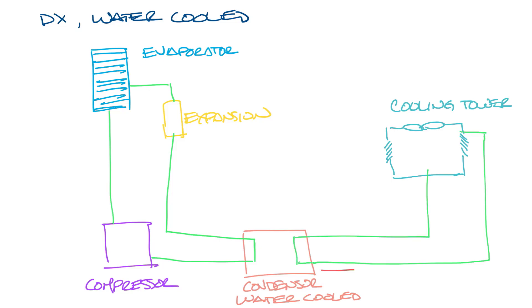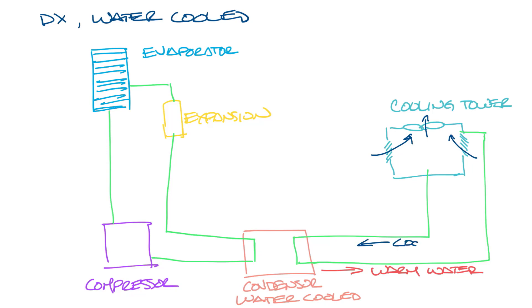Now let's draw in the water loop. The water that is heated up in the condenser travels into the cooling tower. This water is sprayed into the top of the cooling tower. The cooling tower has a fan to draw air across water from the condenser. This causes some of the water to evaporate and cool, and the cooled water falls to the bottom of the tower. And then that water goes back to the condenser to start the process all over again.